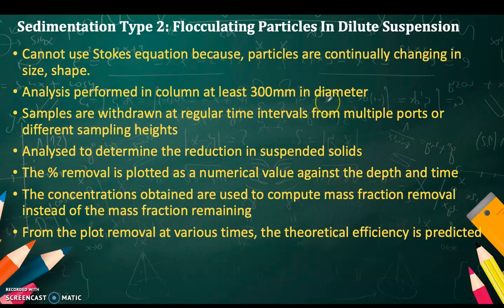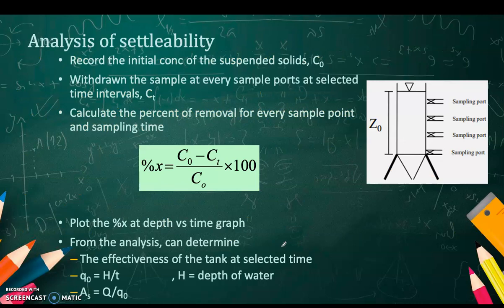Analysis is performed in a column at least 300 mm in diameter. Samples are withdrawn at regular time intervals from multiple ports at different sampling heights. The removal is plotted as numerical values against depth and time. From the plot, removal at various times, the theoretical efficiency is predicted.